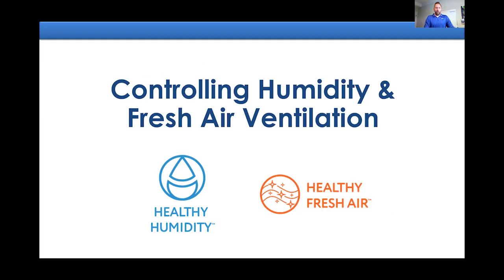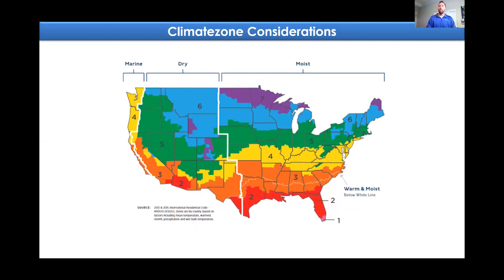The opportunity for ventilating and dehumidifying, specifically looking at this climate zone map, that if you're in climate zones 1A, 2A, 3A, I would even push into 4 and 5A, that we have to really consider when we're bringing that outdoor air in to condition it properly. And that might have to be through a dehumidification system. I know in Houston, I know down in Florida, the coastal environments of Louisiana, I could tell you up into even mid to upper Georgia, that ventilating dehumidification systems are really the way now that are being standardized, even versus ERVs or other mechanical systems.